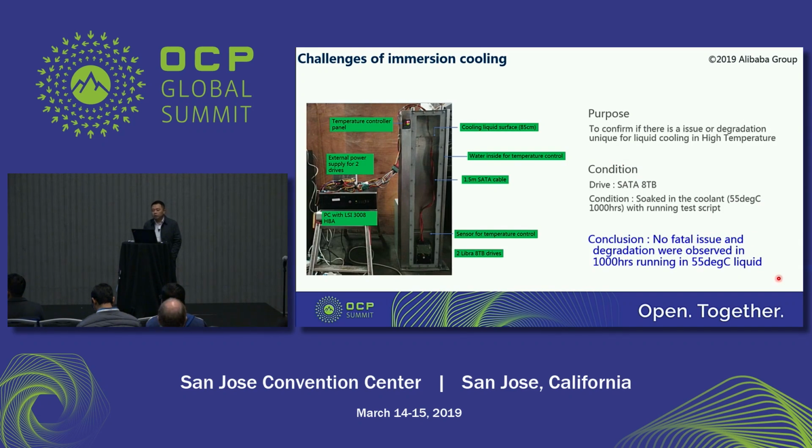To confirm if there is any issue or degradation on TCO for helium HDD fully immersed in the liquid, we designed a test fixture. It can control the temperature, which we set at 55 degrees C. The liquid surface is about 85 centimeters high. After a long-time stress test, we found no fatal issue and no degradation was observed. So the helium HDD is compatible with the liquid. It can work well.